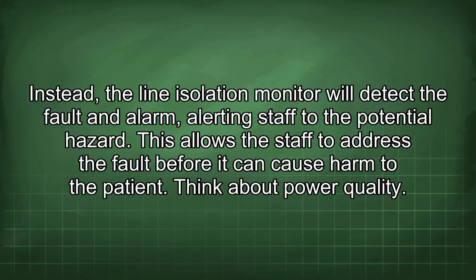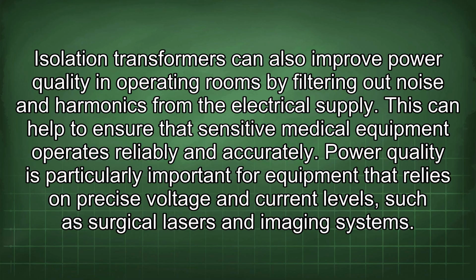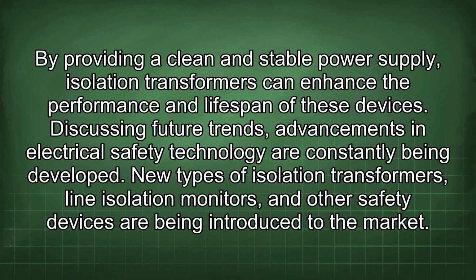Think about power quality. Isolation transformers can also improve power quality in operating rooms by filtering out noise and harmonics from the electrical supply. This can help to ensure that sensitive medical equipment operates reliably and accurately. Power quality is particularly important for equipment that relies on precise voltage and current levels, such as surgical lasers and imaging systems. By providing a clean and stable power supply, isolation transformers can enhance the performance and lifespan of these devices.